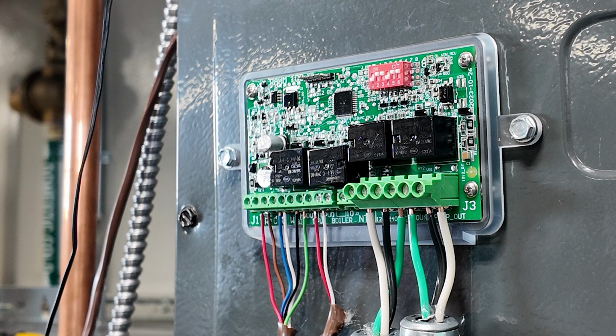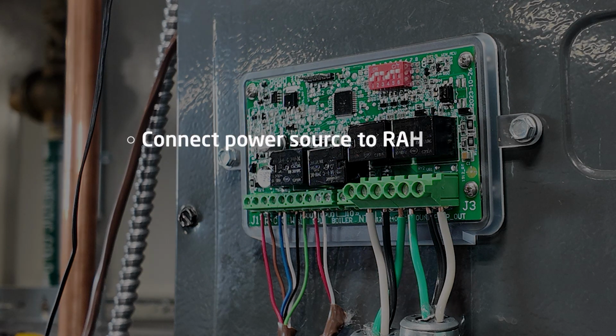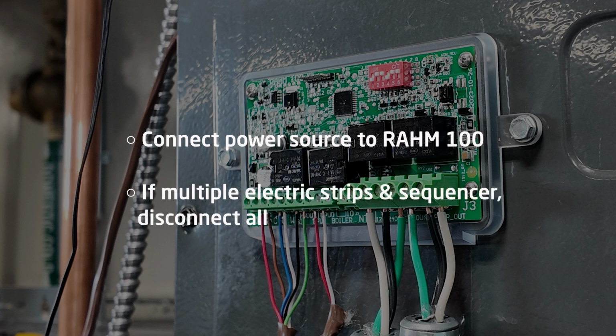Connect the appropriate power source to the mounted RAHM 100 controller. In this install, our pump is a 120 volt pump. If there are multiple electric strips and a sequencer, disconnect all of them to prevent unit sequencing in the first stage of heating.